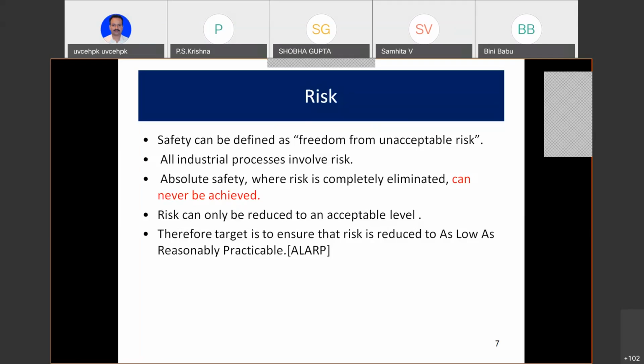And then what happened is, by doing all this, not only instrument people but mechanical, civil, electrical, and all other disciplines, process people, the operating instructions, everything put in place, that 100% risk was brought down to a level we were prepared to accept. So they reduced that risk to some lower value. You will see a diagram of that also. So the instruction for you during design is a very interesting, catchy word, ALARP: as low as reasonably practical. So you have reduced the risk. You cannot eliminate it. And you also have to look at the purse. You cannot go in a senseless way, only looking at the technical side. You have to look at the economics, the operation loss, the operation shutdown value.